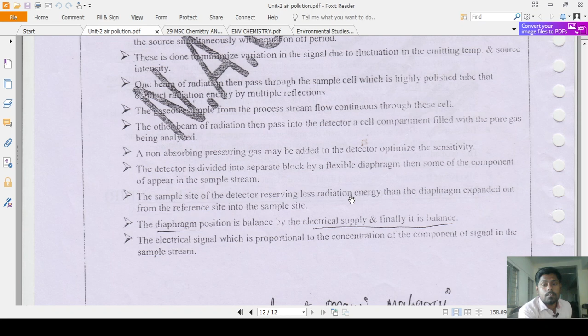The sample side of the detector receives less radiation energy than the reference side, so the diaphragm expands out from the reference side into the sample side. The diaphragm position is balanced by the electrical supply, and finally it is balanced. That means whenever the IR beam is passed through the sample cell, because of the absorption of the IR by the pollutant present in the air sample, the intensity of the IR is decreased, while in the pure gas there is an absence of pollutant, and because of that the intensity of the IR is higher compared to the sample cell.